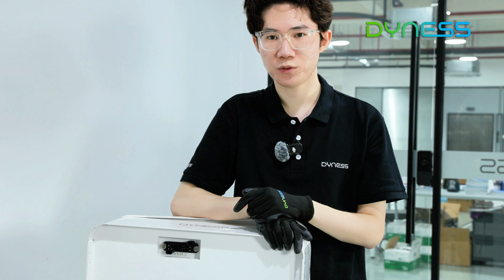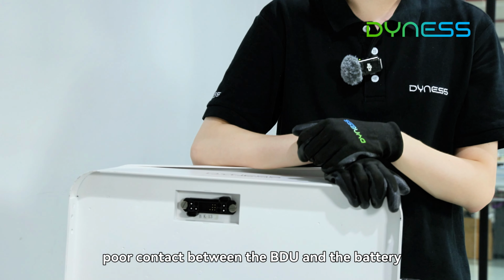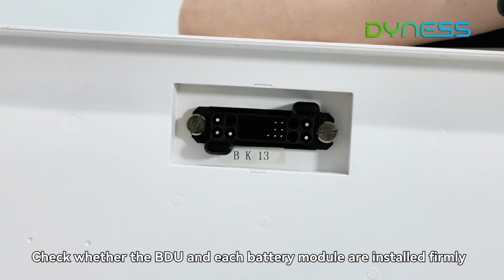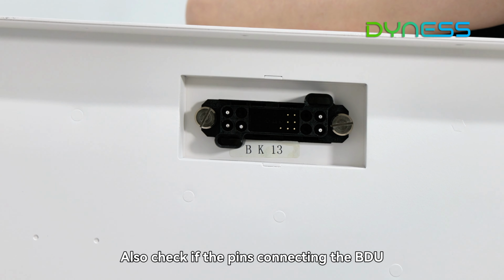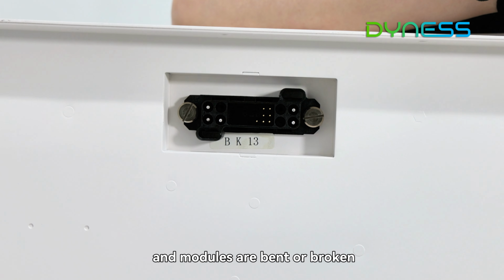Let's look at the second reason: poor contact between the BDU and the battery. Check whether the BDU and each battery module are installed firmly. Also check if the pins connecting the BDU and modules are bent or broken.